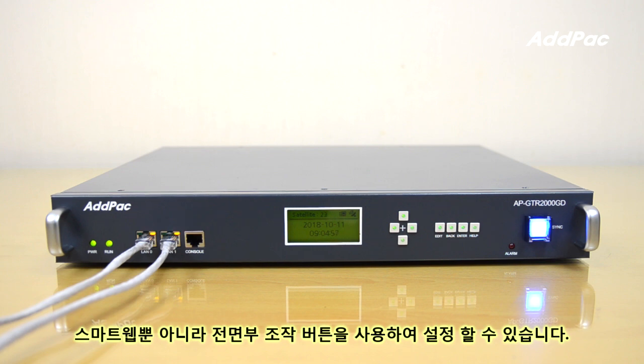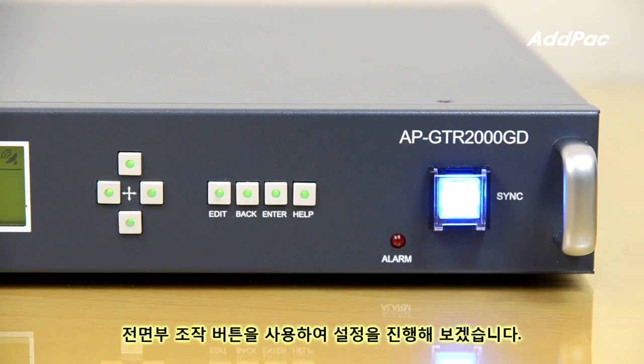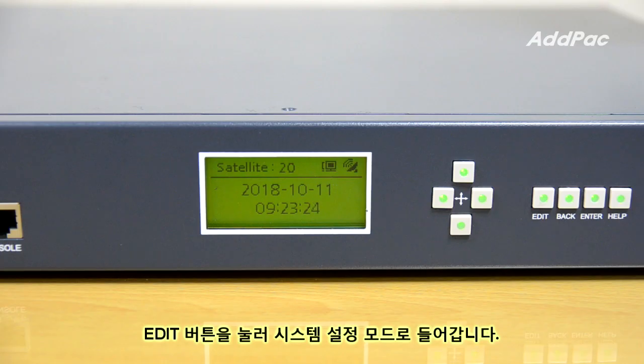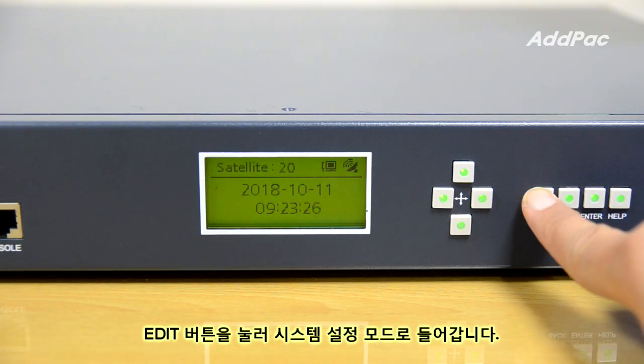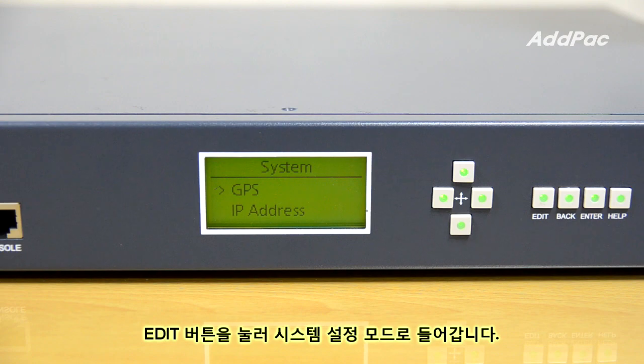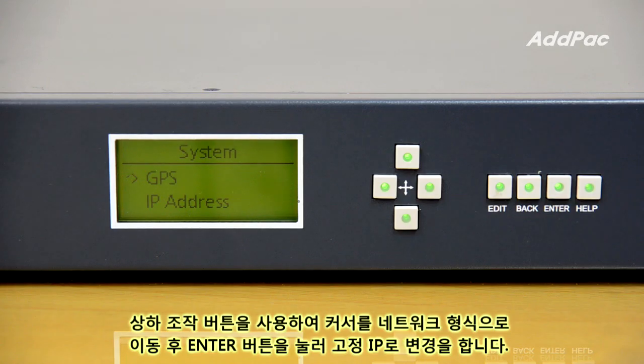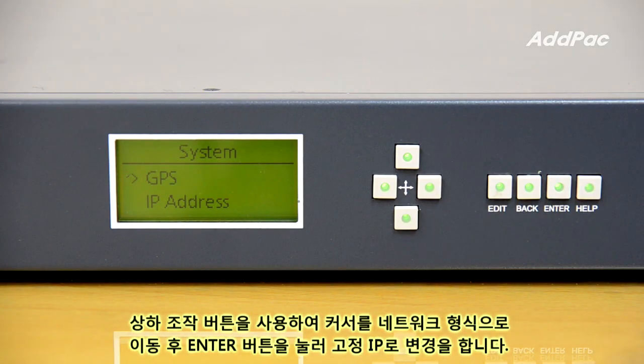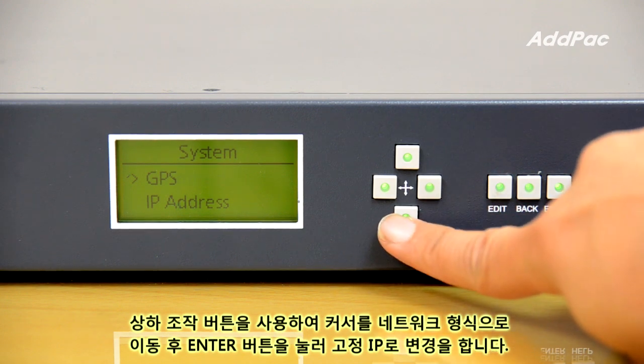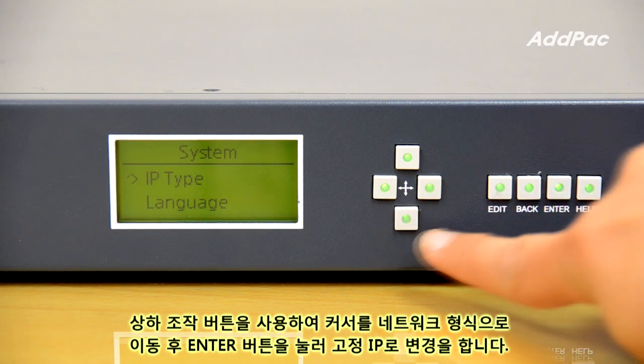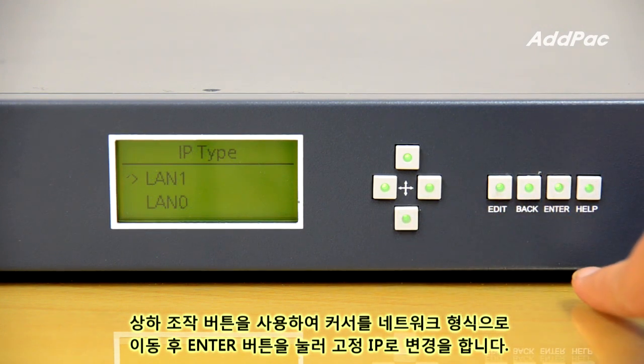You can set simply using the buttons in the front side as well as the Smart Web. Let me start to set using the buttons in the front side of the device. Access System Set Mode by clicking the Edit button. Change to static IP by clicking the Enter button after moving the cursor to network type using the up and down buttons.